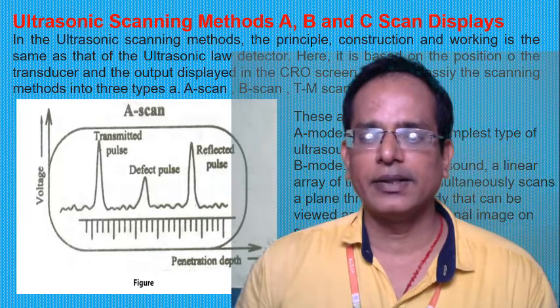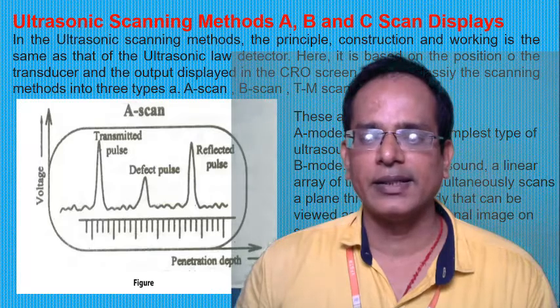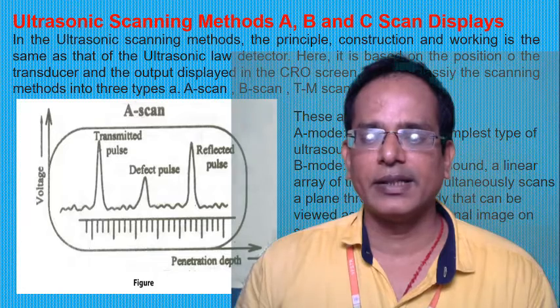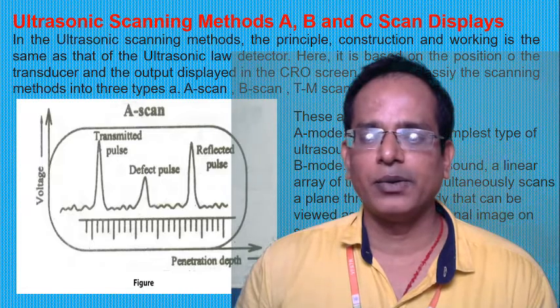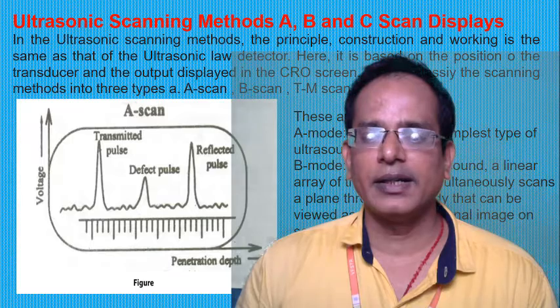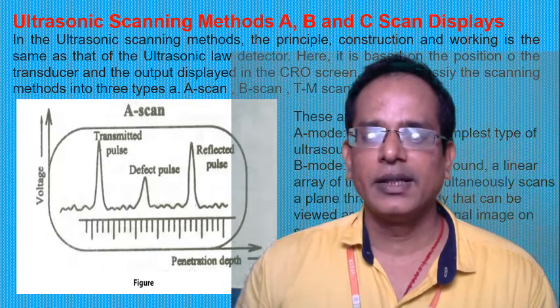B-mode has an array of transducers which simultaneously scan the internal organ as a plane through the body, which can be viewed as two-dimensional images. A-mode provides a signal, B-mode provides images, and M-mode stands for motion images — for example, heart functioning, liver functioning, or viewing a baby inside the uterus — that is the motion display mode.